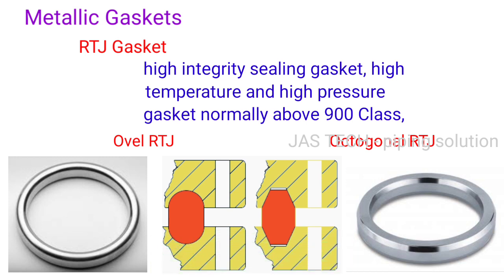Metallic gasket - RTJ (Ring Type Joint gasket): A high integrity sealing gasket used in high temperature and high pressure applications, normally above Class 900. There are two types generally used: Oval RTJ and Octagonal RTJ gasket.